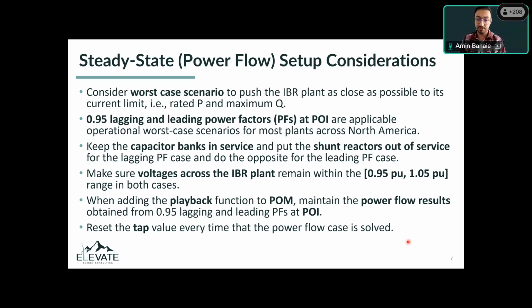Another very important factor that I've seen a lot, where many people do it wrong when setting up the load flow cases, is that when setting the lagging and leading case, make sure that the voltages across the plant remain within 5% of the rated voltage. If you are increasing Q generation of the inverters, and you see that the voltage at the inverter terminal goes to, let's say, 1.1, then that means that plant is not able to meet 0.95 lagging power factor. So you may want to end up at a larger power factor, let's say 0.99 or 0.98, and that would be your worst case scenario rather than 0.95.